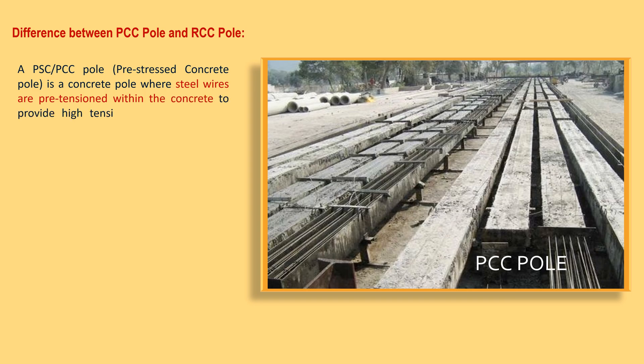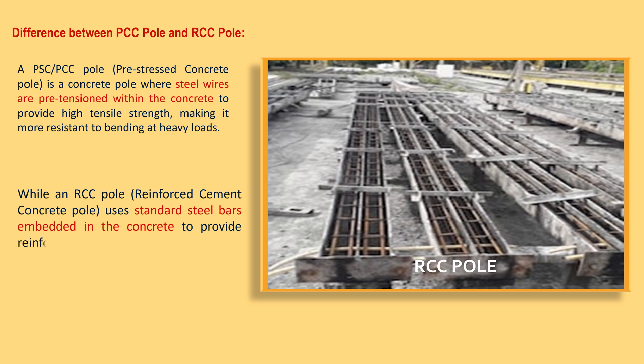The difference between PCC and RCC poles: a PCC pole has steel wires pre-tensioned within the concrete to provide high tensile strength, making it more resistant to bending at heavy loads. An RCC pole uses standard steel bars embedded in the concrete to provide reinforcement, but without the pre-tensioning process.